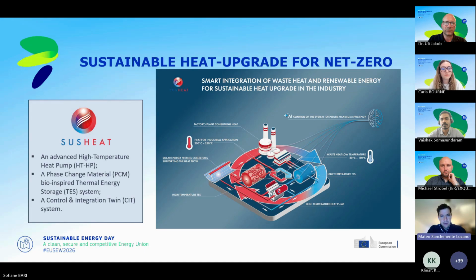In our project, we are working with an industrial partner that currently has a heat pump operating at around 150, 160, even 180 degrees. With the SUSHEAT project, we want to extend the upper temperature level to 200 and 250 degrees, to demonstrate the technology of the heat pump and the thermal energy storage up to TRL 5. The concept also includes concentrating solar power, in this case Fresnel linear collectors, that can work in parallel or in series with the heat pump to provide the required process heat to the factory. We are targeting applications in the food, paper, chemical, and pharma industries, where the steam level is not so high.